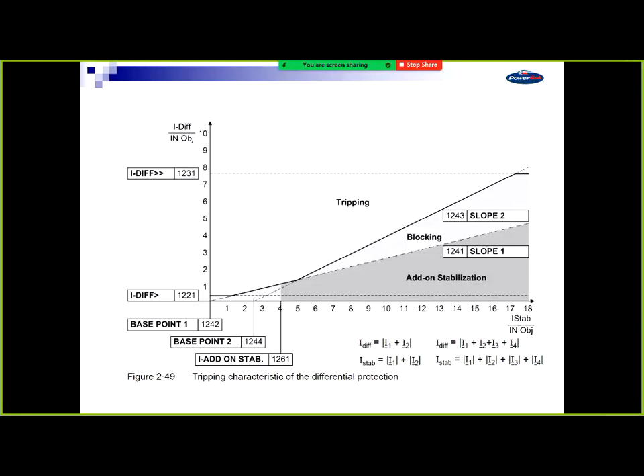There's a picture coming up which will show what internal faults look like, but here you've got that 1221, that's your pickup. So we put a safety margin on there of 20 or 30%. We generally follow what the manufacturer suggests. You've got one slope down the bottom line there through the origin. You've got a second steeper slope starting at that base point 2 at a second one. Anything above that line we trip, anything below that line we don't trip.